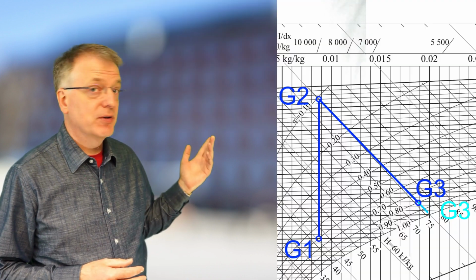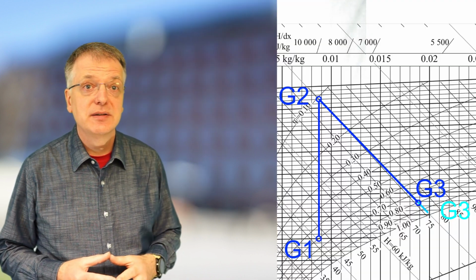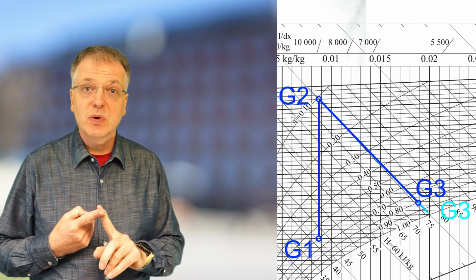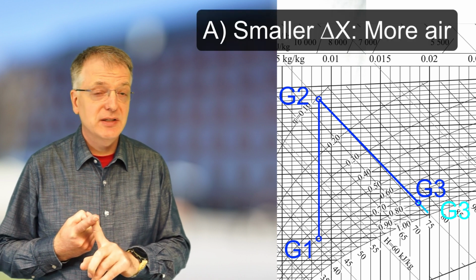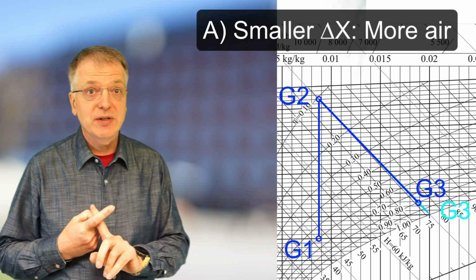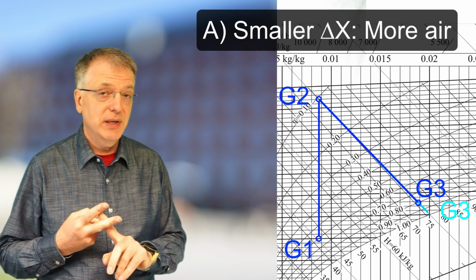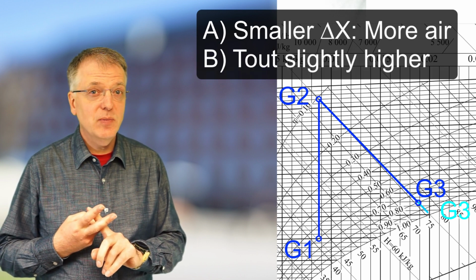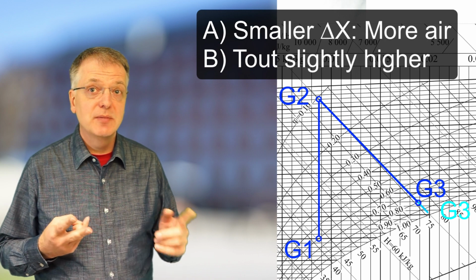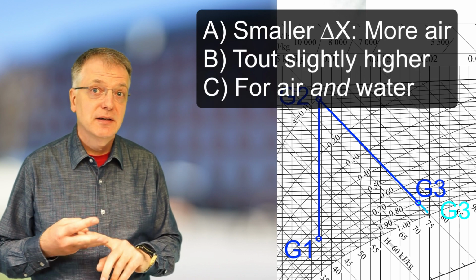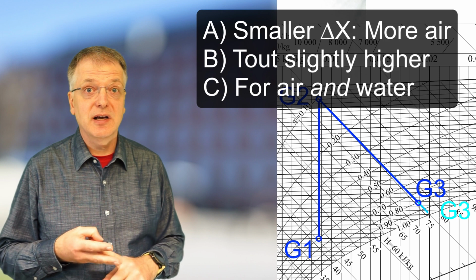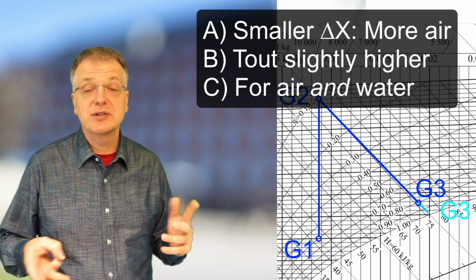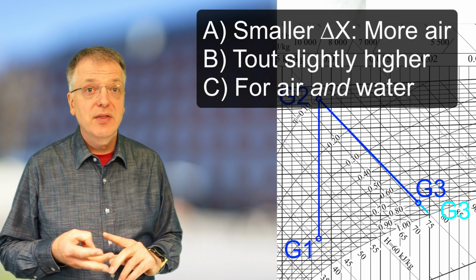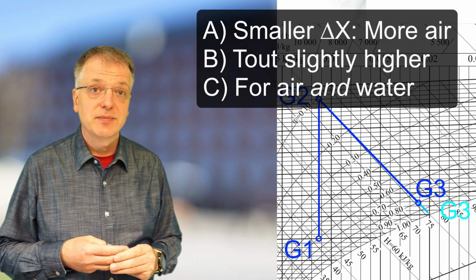When we change our graphical solution, we see that A, the change in water content x3 minus x2 decreases. We will thus need more fresh air. B, the outgoing air is slightly warmer, which means we will need more energy. And C, the evaporated water is also slightly higher, it having the same temperature as the outgoing air, and thus a bit more energy is needed.